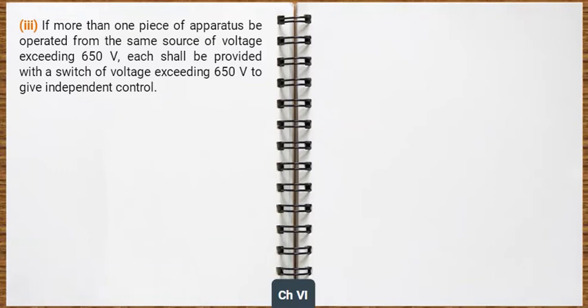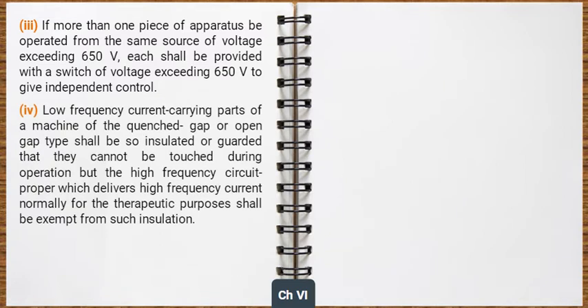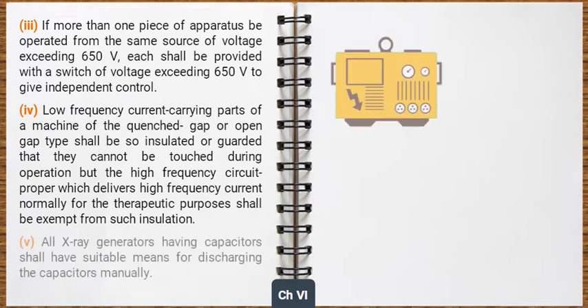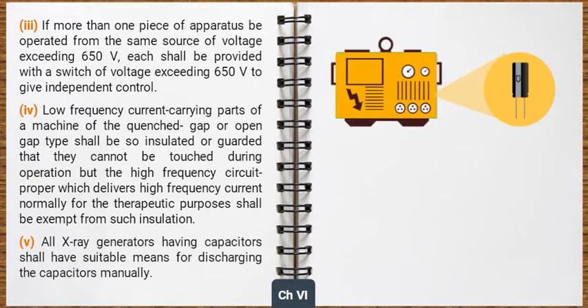If more than one piece of apparatus is operated from the same source of voltage exceeding 650 volt, each shall be provided with a switch of voltage exceeding 650 volt to give independent control. Low-frequency current-carrying parts of a machine of the quenched gap or open gap type shall be so insulated or guarded that they cannot be touched during operation, but the high-frequency circuit proper, which delivers high-frequency current, normally for therapeutic purposes, shall be exempt from such insulation. All X-ray generators having capacitors shall have suitable means for discharging the capacitors manually.